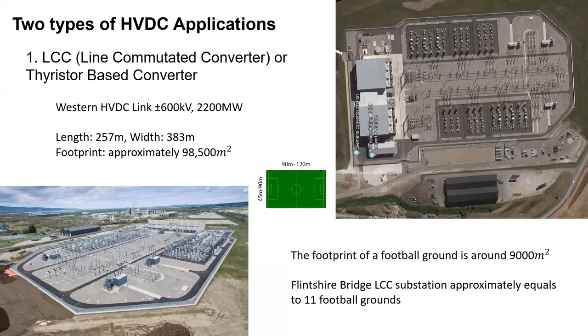So HVDC technology has two sub-technologies, or application types. The first one is LCC, which stands for line commutated converter. It uses thyristors and requires more space than the other application, which is VSC.